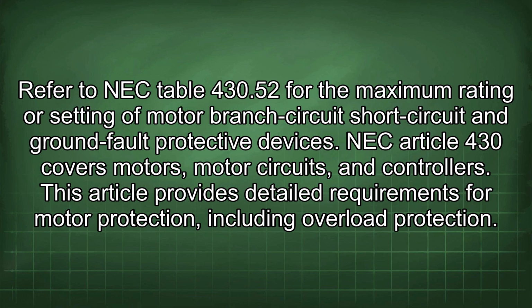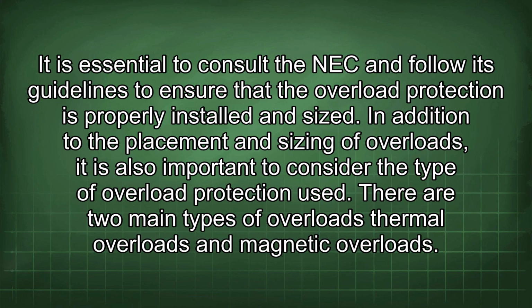Refer to NEC Table 430.52 for the maximum rating or setting of motor branch circuit, short circuit, and ground fault protective devices. NEC Article 430 covers motors, motor circuits, and controllers. This article provides detailed requirements for motor protection, including overload protection. It is essential to consult the NEC and follow its guidelines to ensure that the overload protection is properly installed and sized.